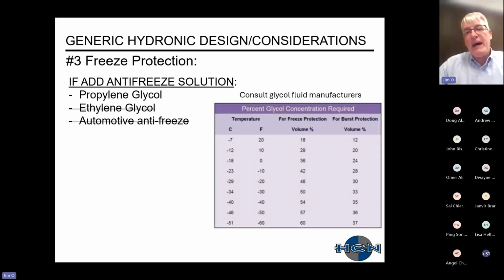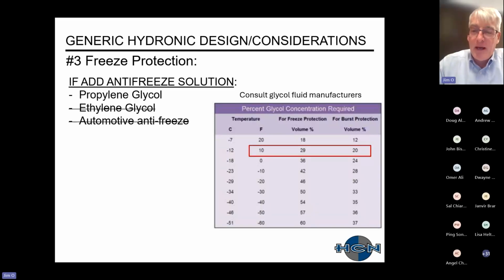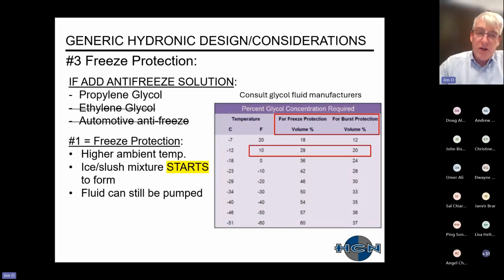There are different manufacturers that produce propylene glycol. Each of the manufacturers has a chart, shown here in an ugly purple and grayish color that I'm terrible at describing. Essentially what you have is the ambient temperature, and then you have volume percentages for freeze protection versus burst protection. I just want to go through the difference between freeze and burst protection.